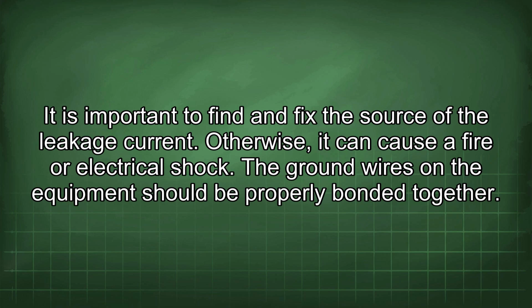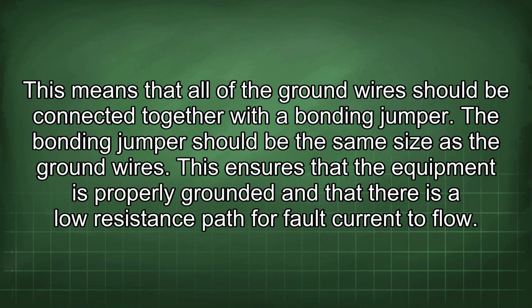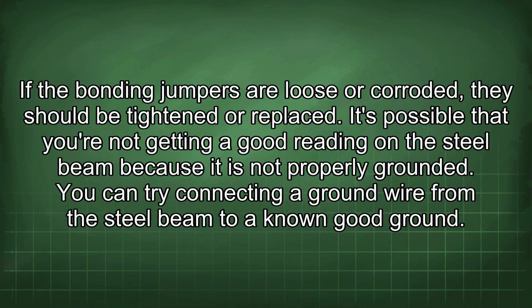The ground wires on the equipment should be properly bonded together. This means that all of the ground wires should be connected together with a bonding jumper. The bonding jumper should be the same size as the ground wires. This ensures that the equipment is properly grounded and that there is a low resistance path for fault current to flow. If the bonding jumpers are loose or corroded, they should be tightened or replaced.